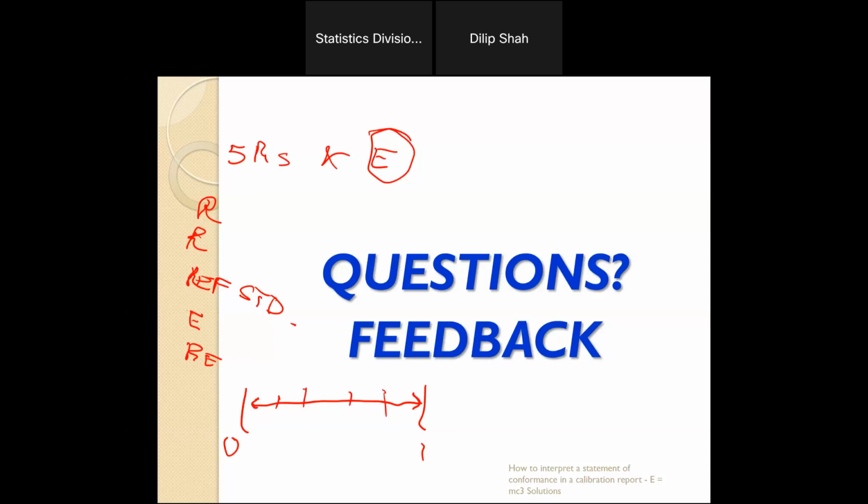And then the calibration interval, the calibration provider should not impose a calibration interval. The consumer of the equipment should specify, because the supplier doesn't know how you use the instrument.